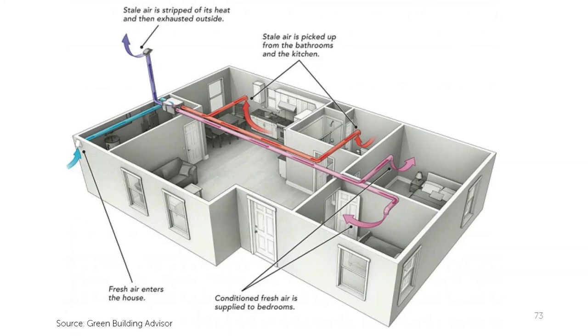Good system design also considers where the fresh air needs to come from. Where are the exhaust air outlets on the exterior of the home? That includes flue pipes for heating systems, radon fans, and chimney terminations. What about exterior generators or vehicle exhaust locations? Certainly wouldn't want to bring fresh air from there.